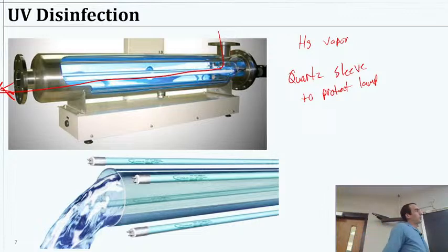So there is a pretty large expense, because I mentioned cleaning the bulb itself is not really practical. Well, you have to clean that quartz sleeve eventually because it will just get caked up with organic matter that's going through the water, with mineral deposits, with all that UV light. There's going to be some temperature difference, a lot of reactions happening. So it does get caked up, and then it will block light from going through it. So they do have to be cleaned every so often.